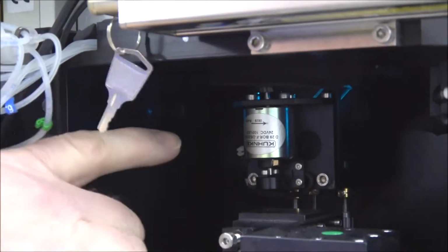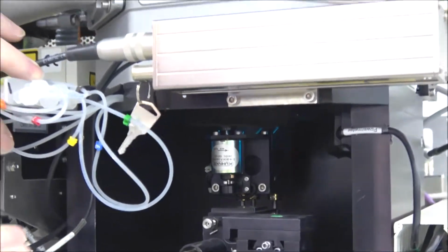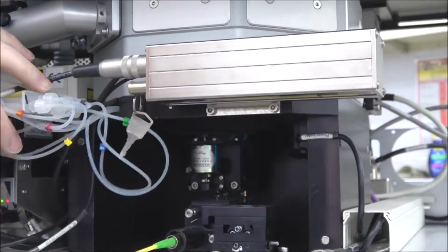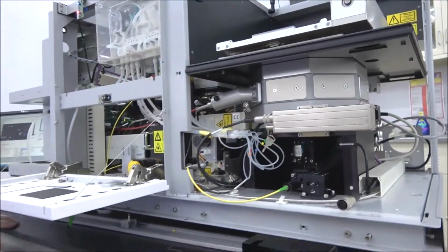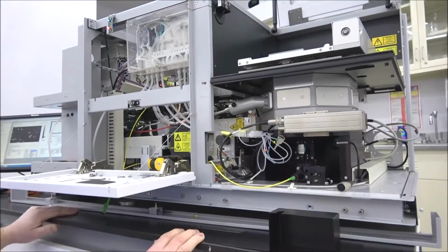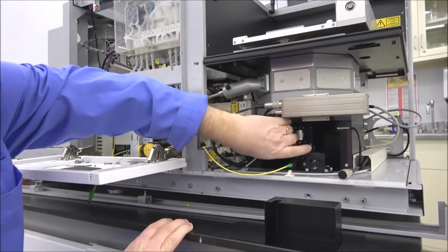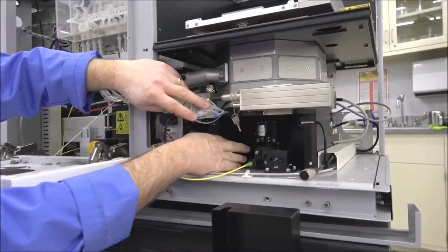It's bouncing off the mirror and going upwards into our subject, and also it's passing through into the meter, and that's what's actually reading it while it's being calibrated. If that's not lined up, then you'll get some really poor readings.